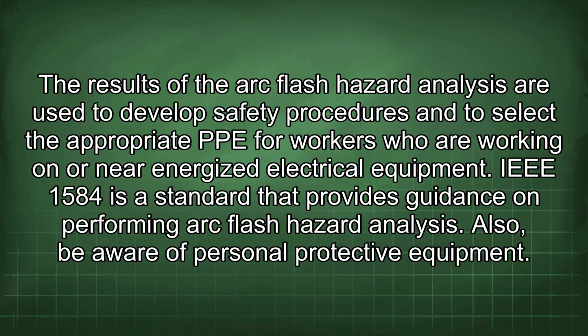The results of the arc flash hazard analysis are used to develop safety procedures and to select the appropriate PPE for workers who are working on or near energized electrical equipment. IEEE 1584 is a standard that provides guidance on performing arc flash hazard analysis. Also, be aware of personal protective equipment.